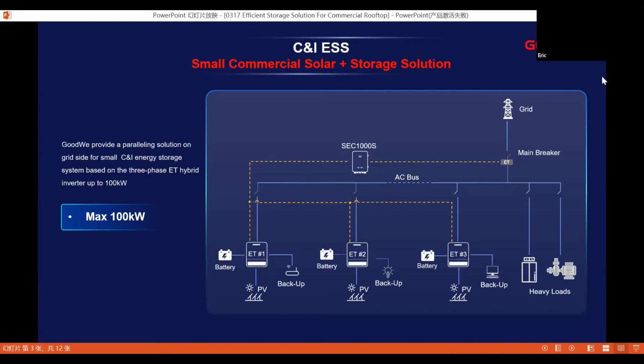Like the picture shows, we can see three ET hybrid inverters. We can connect the PV panels to each ET series, and the output of the ET series can be connected in parallel to the grid. The feature of this solution is that the maximum capacity of a single unit is 10 kilowatts, and the maximum of the system is 100 kilowatts. So that means the maximum number of ET series units is 10 — you can connect 10 pieces of ET series in parallel on the same grid.